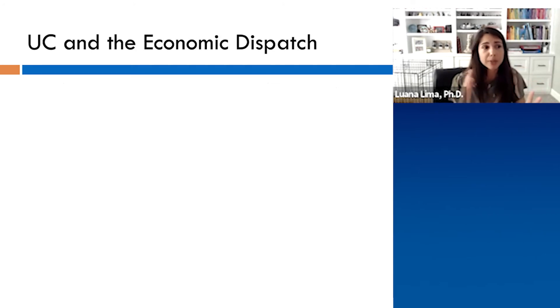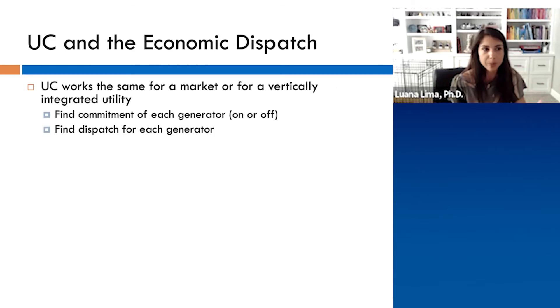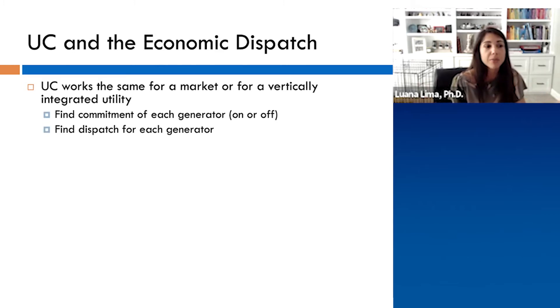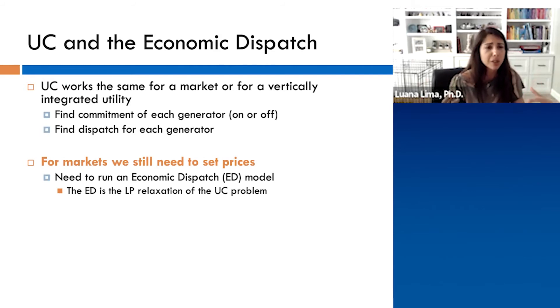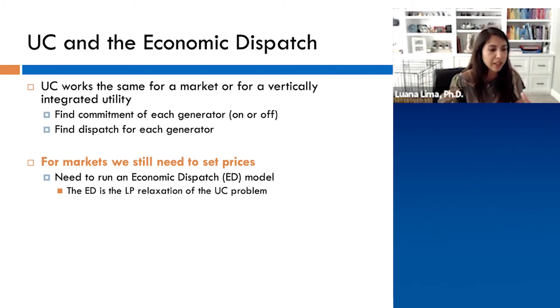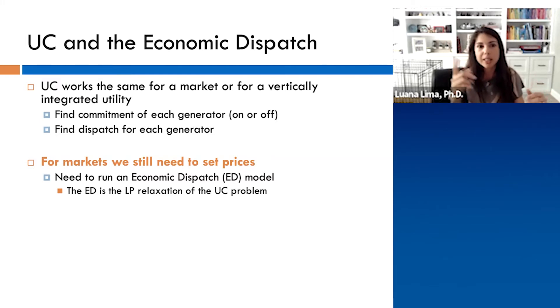Alongside unit commitment, we have what we call economic dispatch. The unit commitment works the same for a market or a vertically integrated utility — it finds whether each generator is on or off, and finds the dispatch for each generator. For markets, since we still need to set prices, we also run the economic dispatch model. The economic dispatch is basically the LP relaxation of the unit commitment problem. The unit commitment problem is a mixed-integer optimization model, because you have integer variables — zero meaning the generator is offline, one meaning it is online.